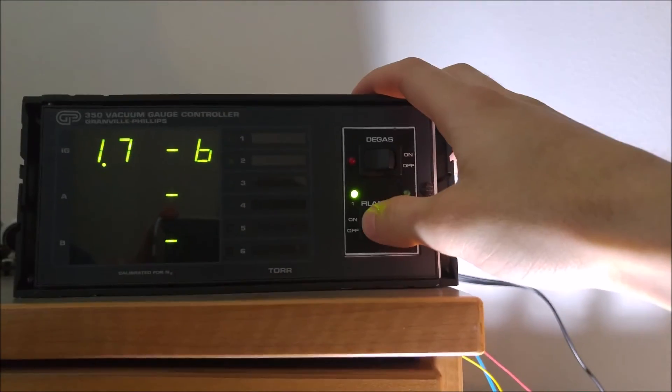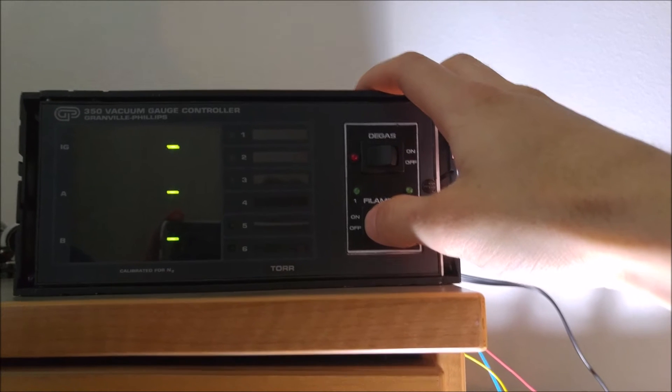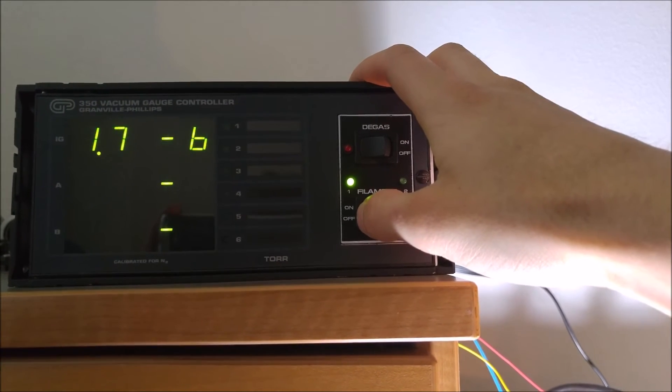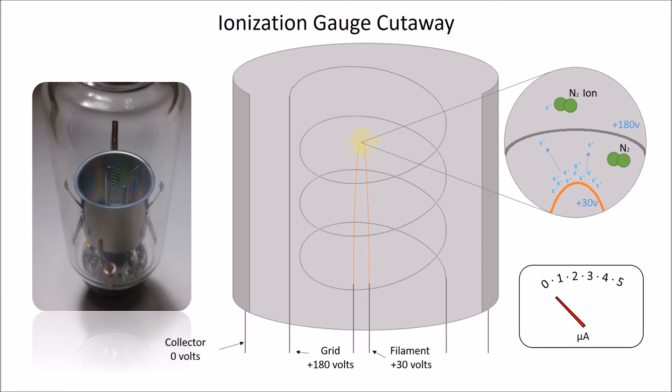The gauges cannot work at atmospheric pressures because the oxygen in the atmosphere would burn out the filament. The pressures you see here are only relative because I've not calibrated the gauge yet. An ion gauge works by counting gas particles in a vacuum. The less particles, the better the vacuum.